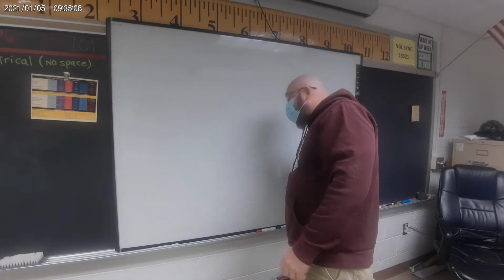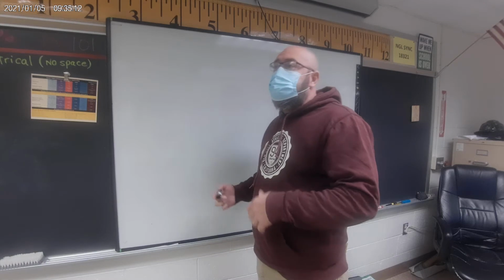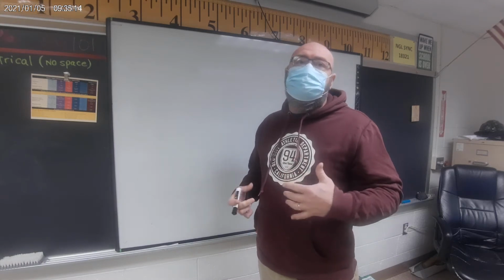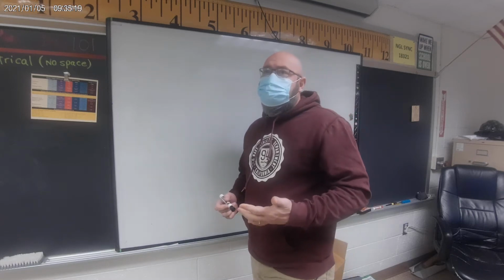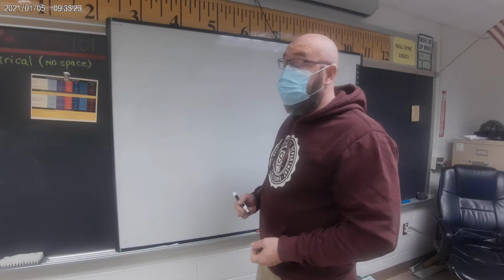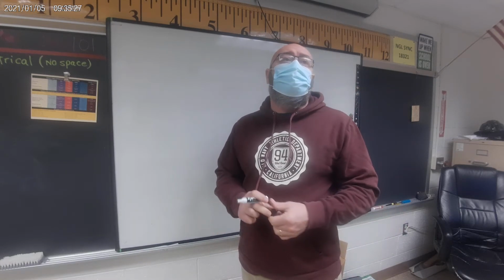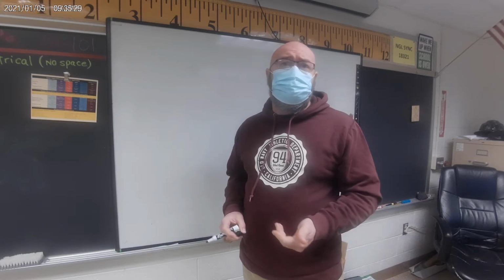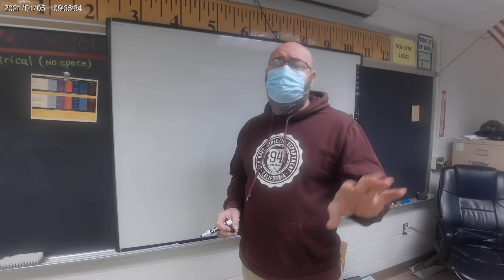Today we're going to go over how to calculate how much heat we need for a room. In this one, we're going to be dealing with electric baseboard heat. The first thing to remember is where to put the heat. Ideally, electric baseboard heat goes under a window, in the coldest spots in the room: windows and outside walls. That's where we're installing the heat.